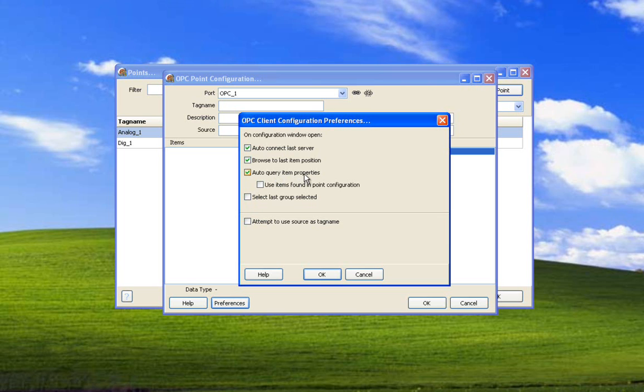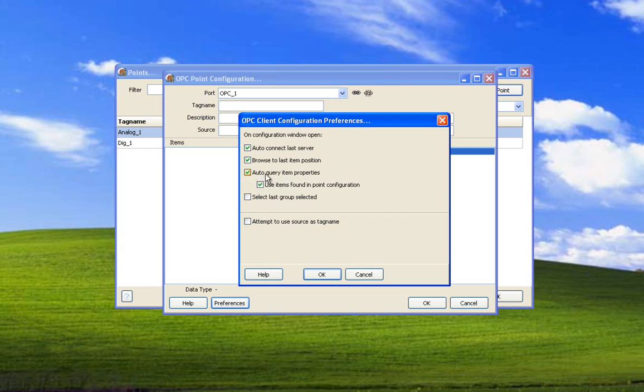Auto query item properties is because an item in OPC has many attributes or can have many attributes. The minimum is six. And some of those attributes we will use or can use inside of the HMI. Use items found in point configuration. What this means is when we auto query these item properties, if it comes back with item properties that we can use, like engineering units or the access rights like read or write, we can just use those properties instead of having to configure them again.